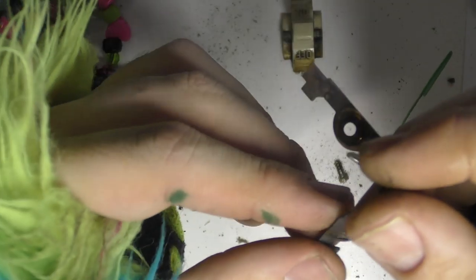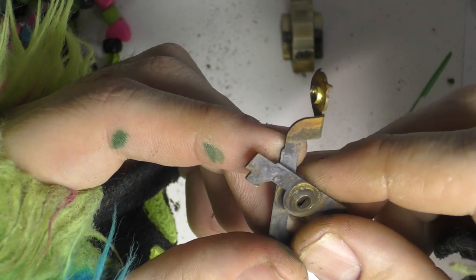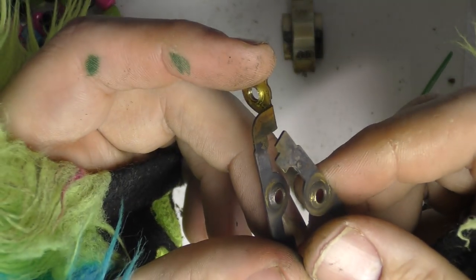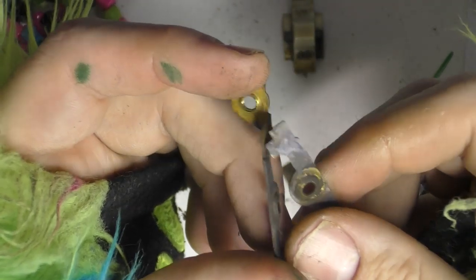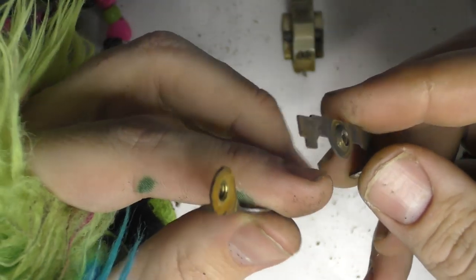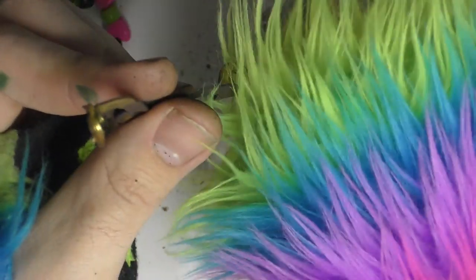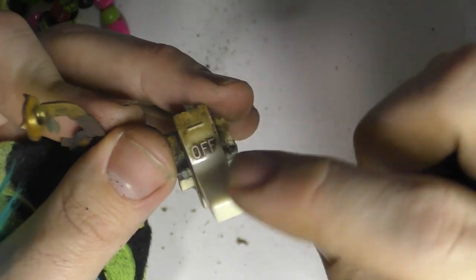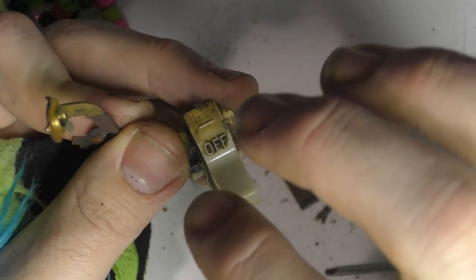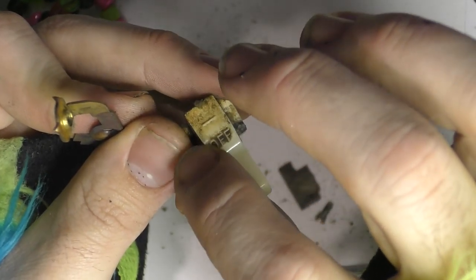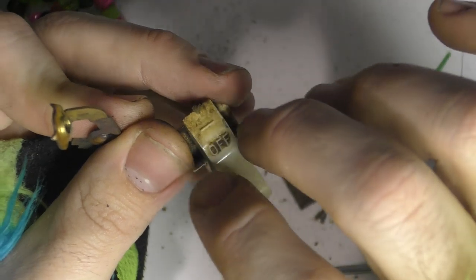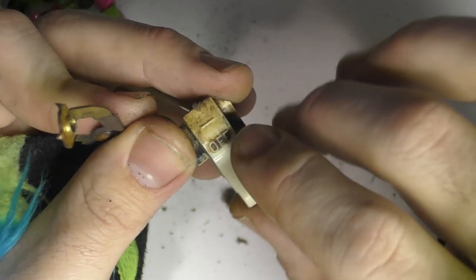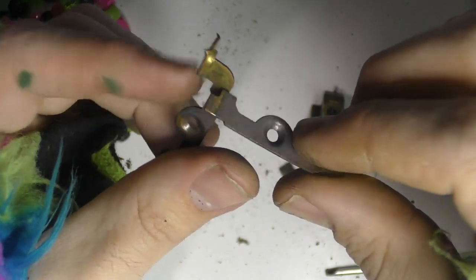So now I'm going to say that the switch heated up. Parts deformed. It lost contact. And that was the end of it. That's all that probably happened. There doesn't seem to be any sign of a short circuit. I've had switches hooked up to short circuits before. And you will see black residue coming out of the switch. You don't even have to take it apart to know that something happened in there. I don't see any sign of that.